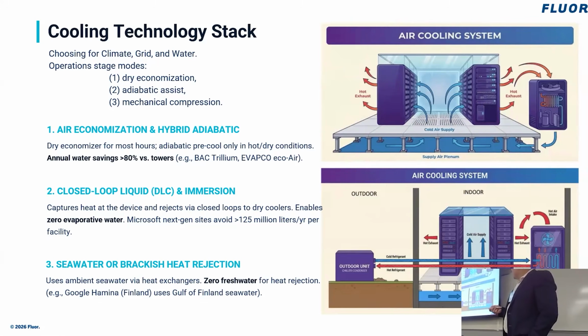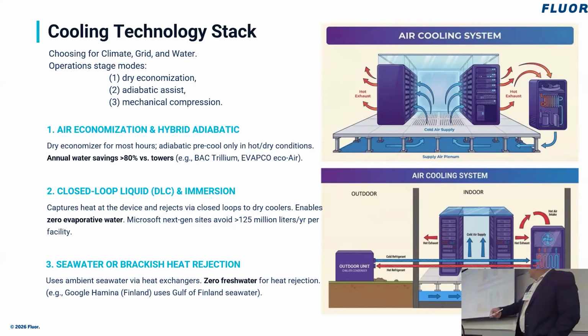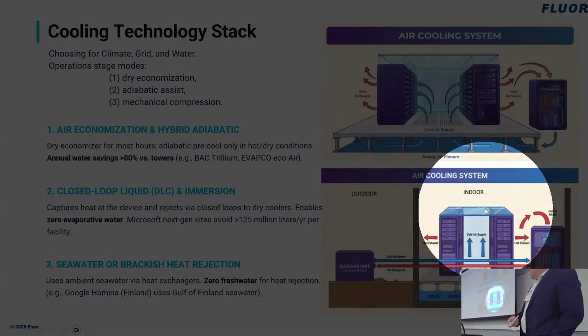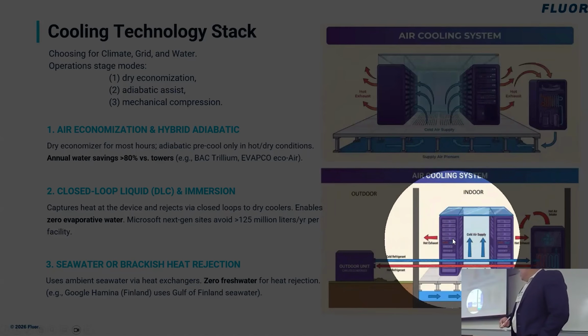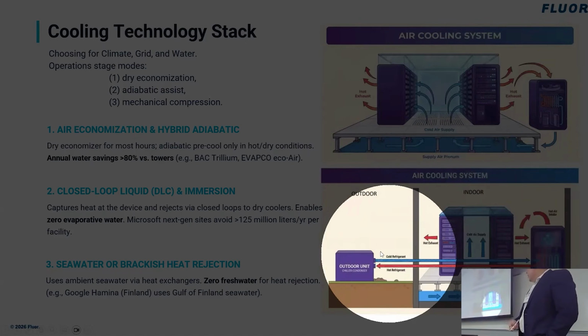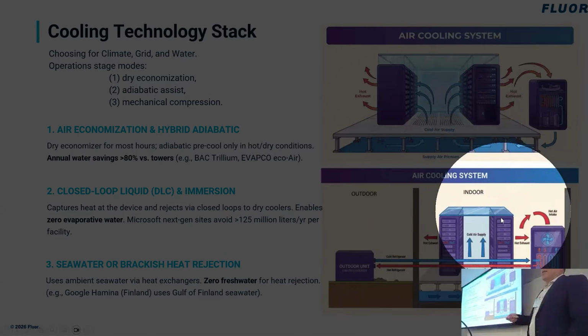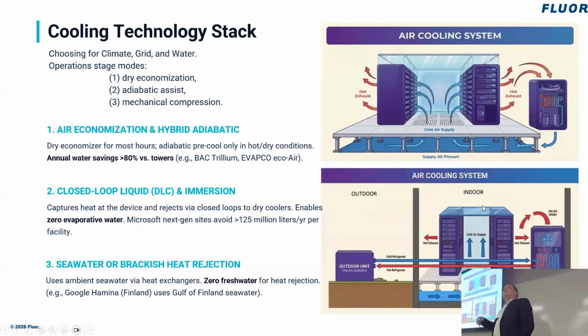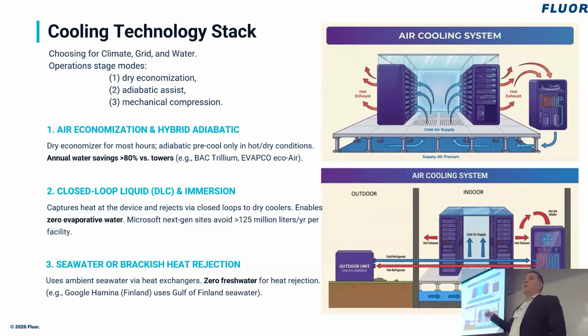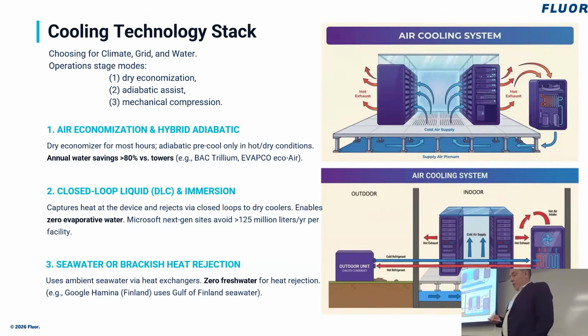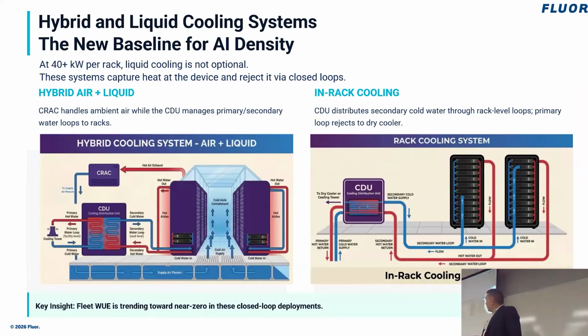But when the air system is not enough, this second drawing shows when we need to recover heat beyond what just air can handle. There's another system using, for example, chillers, which is another optimization because of the increasing capacity of heat. But when that's not enough, we need to go to water or a combination of water and air heat recovery, which is the next system.